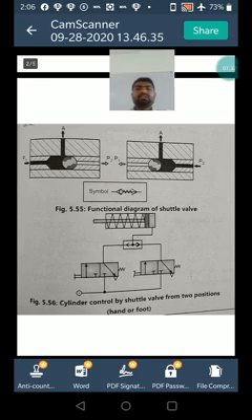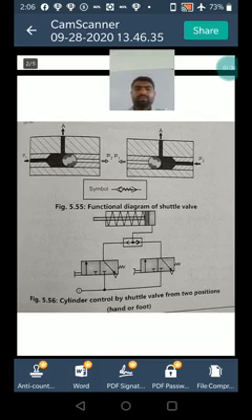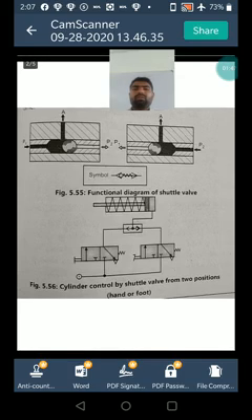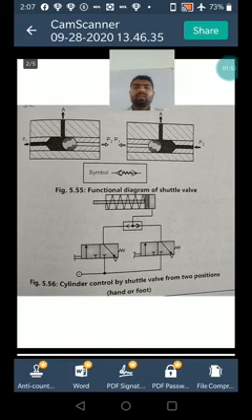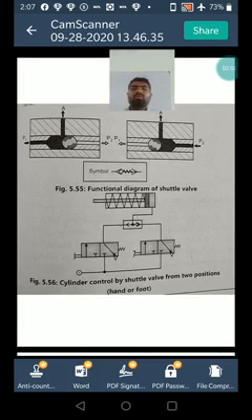The next diagram is shuttle valve. This is a double check valve, figure shows 5.55. In that figure, two inlets and one outlet are shown. The first position P1 is loaded by air while P2 is connected to the exhaust. Hence, the flow flows from P1 to outlet A, and in the other one flow is from P2 to A.